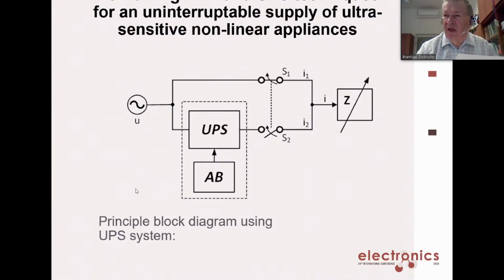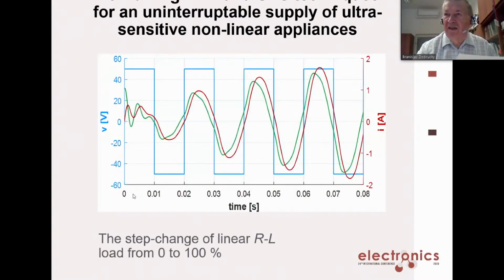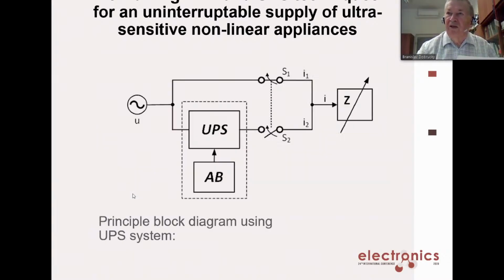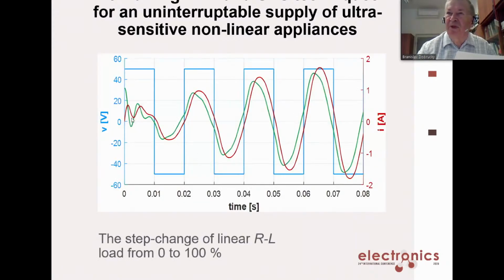This is the classical system, but during step changes with the transfer switches between the network and the UPS, there is sometimes a problem with transients of current and voltage, as you can see in this picture. When the step change is from 0 up to 100%, this is the problem.